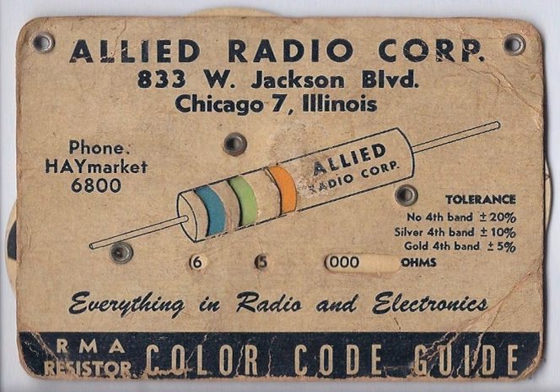Wires may be color-coded to identify their function, voltage class, polarity, phase, or to identify the circuit in which they are used. The insulation of the wire may be solidly colored, or where more combinations are needed, one or two tracer stripes may be added. Some wiring color codes are set by national regulations, but often a color code is specific to a manufacturer or industry.